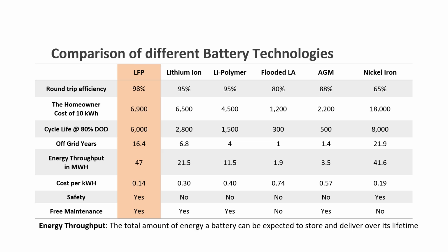Because of the long life cycles and the chemistry itself, the cost per kilowatt hour of LFP is less than half that of lithium ion. Compared to polymer, flooded lead acid, and AGM, there's really no comparison to be made. The only one that's close is nickel iron at 19 cents a kilowatt hour.